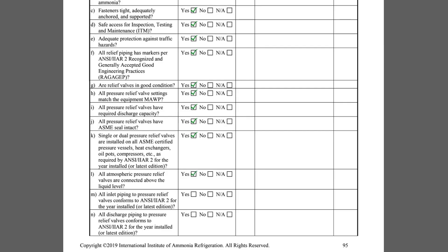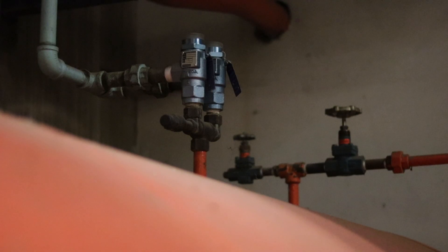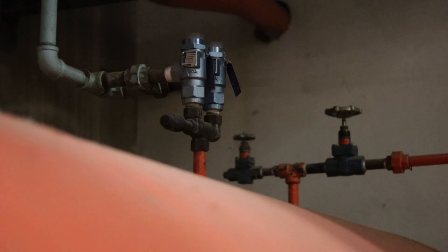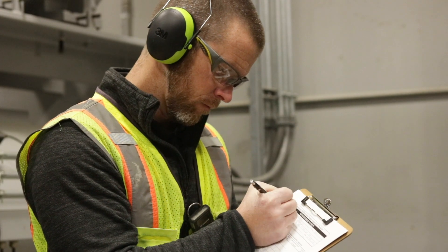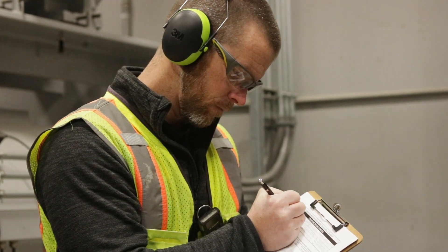Relief valves that discharge to the atmosphere must be connected above the liquid level of the equipment they are protecting. Item L asks if this is true for the relief system being inspected.